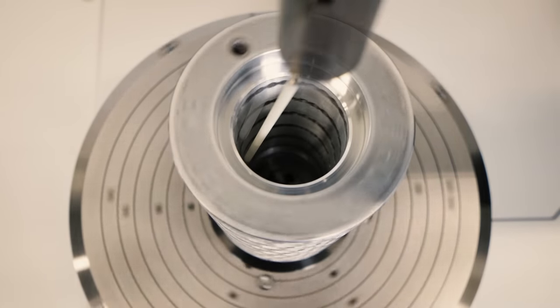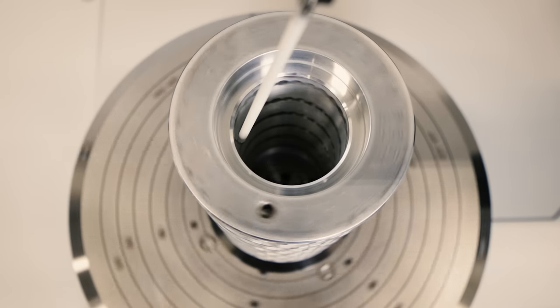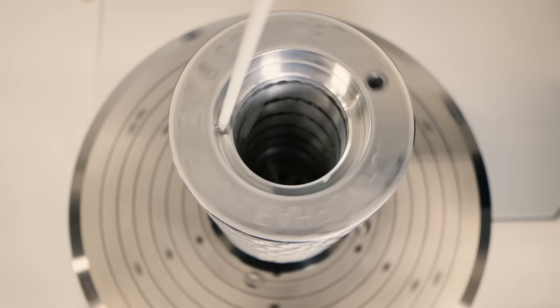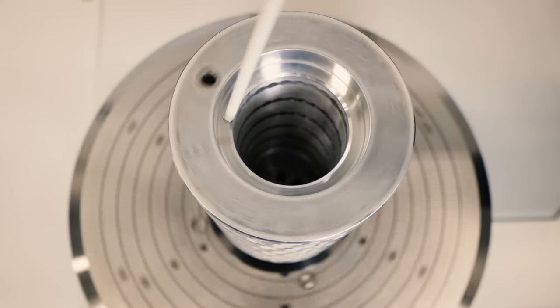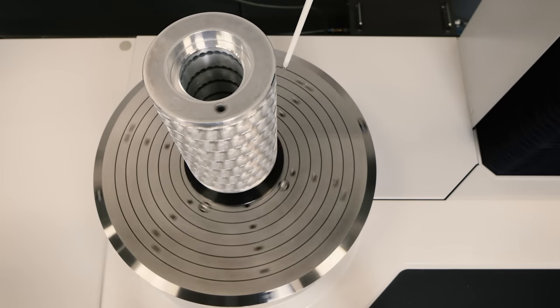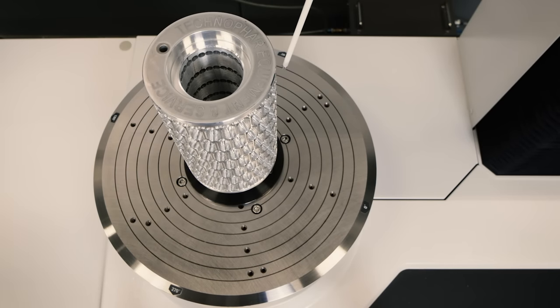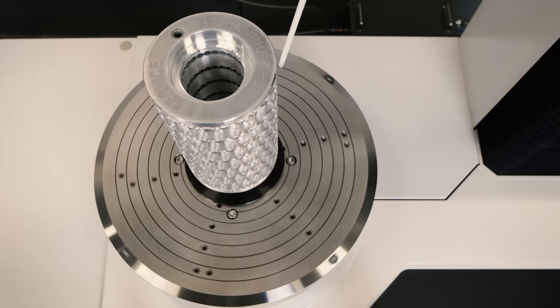For instance, measuring deep inside a thick-walled workpiece can be done with a newly developed three-position motorized sliding axis on the detector holder. This helps avoid workpiece collision while enabling continuous automatic measurement.